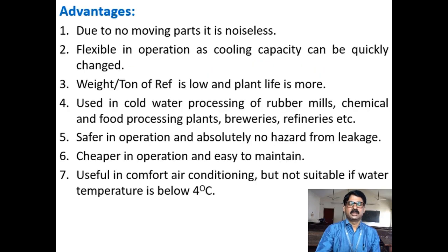Coming to the advantages, due to no moving parts it is noiseless, and it is flexible in operation as cooling capacity can be quickly changed. Weight per ton of refrigeration is low and plant life is more. It is used in cold water processing of rubber mills, chemical and food processing plants, breweries and refineries, etc. It is safer in operation, with absolutely no hazard from leakage. It is cheaper in operation and easy to maintain. It is useful in comfort air conditioning but not suitable if water temperature is below 4 degrees Celsius.